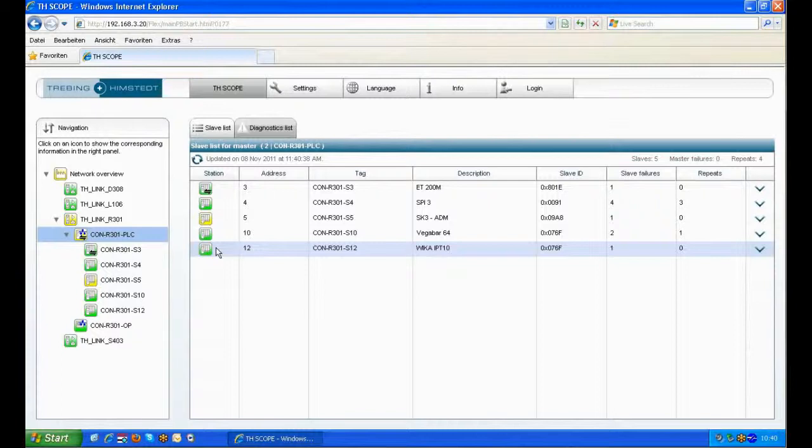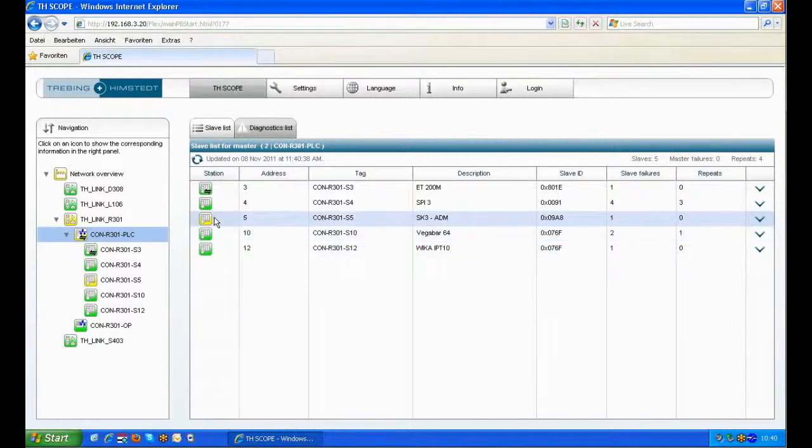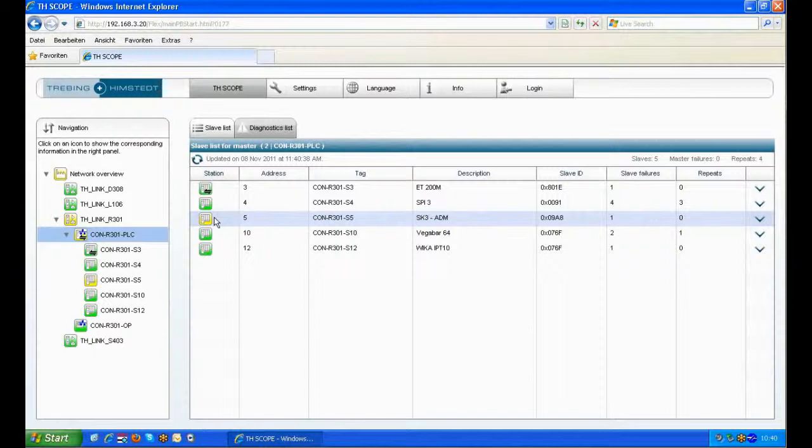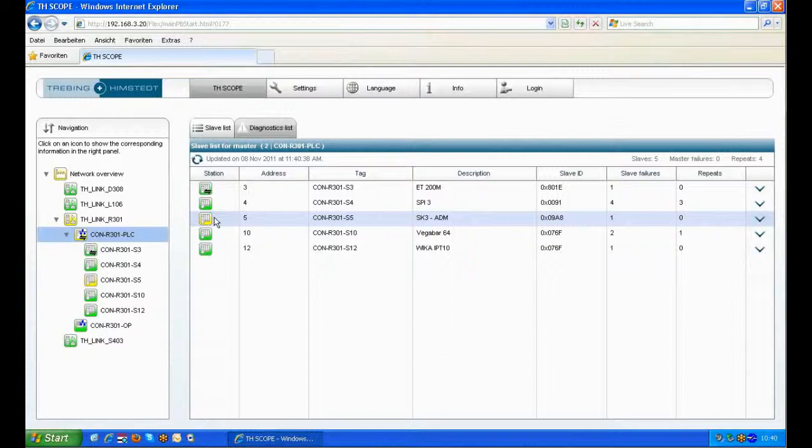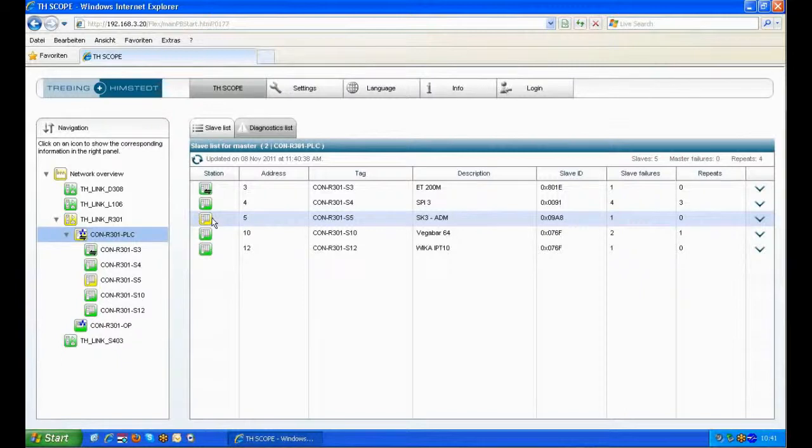The devices are in good status with green icons, but the Advanced Diagnostic Module (ADM) from SK3 is telling us some diagnostic information with a yellow color. The station address 5 on the DP network is used for the ADM to get this information from SK3.